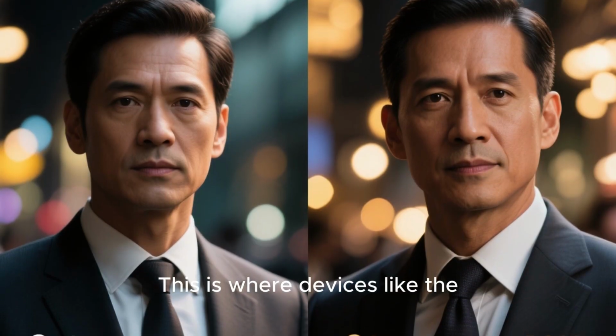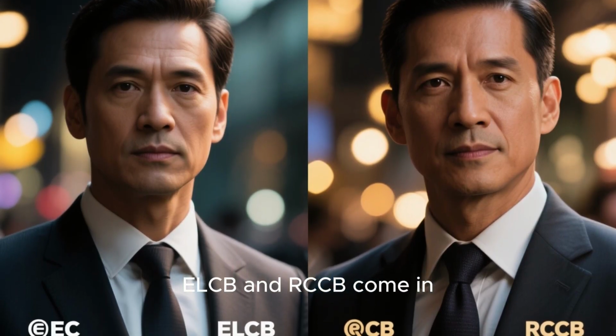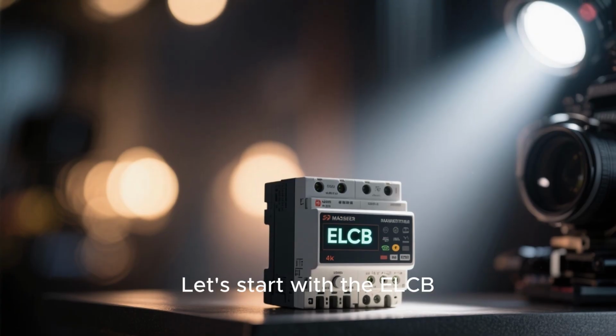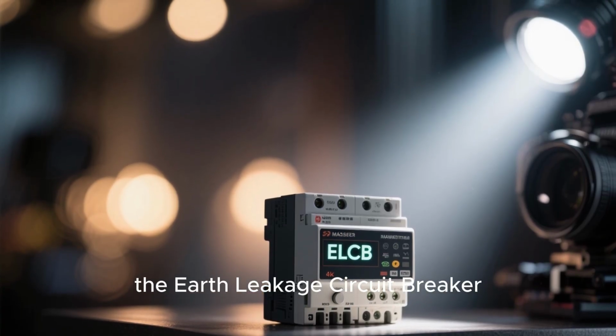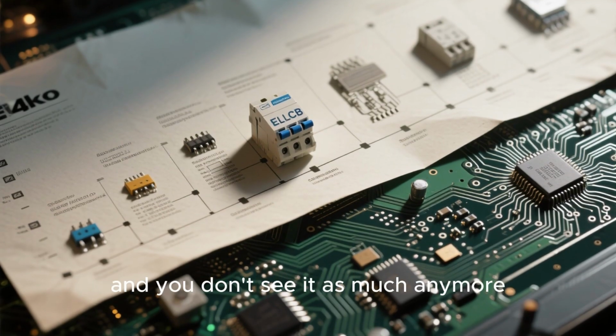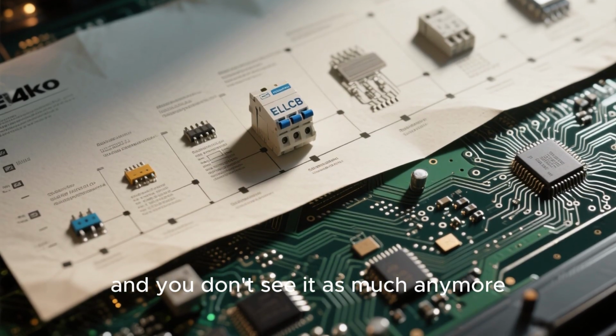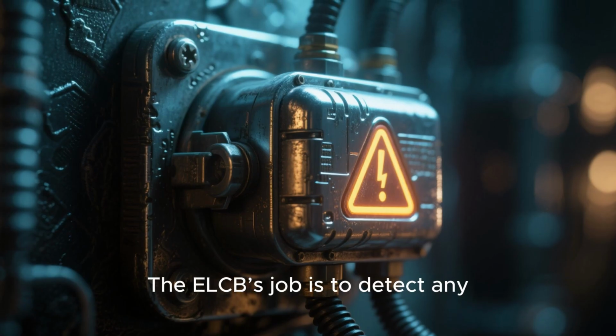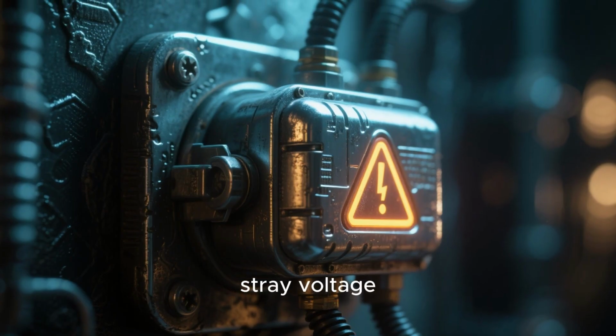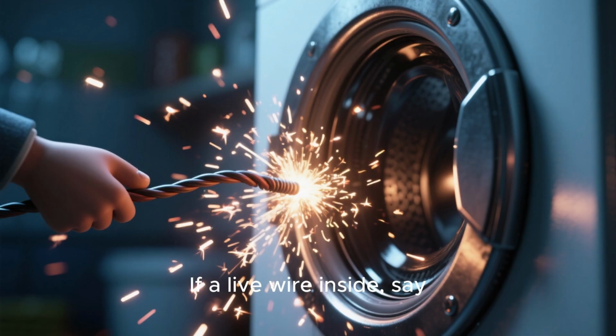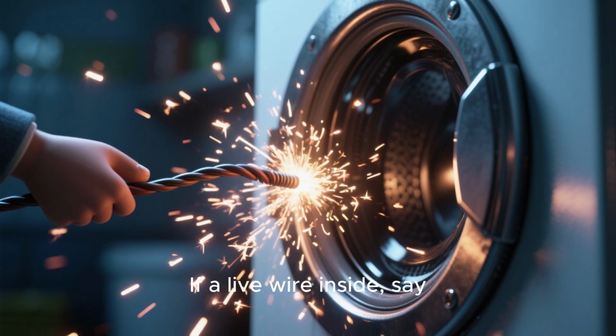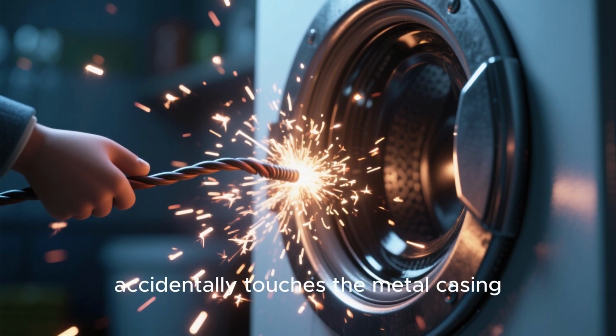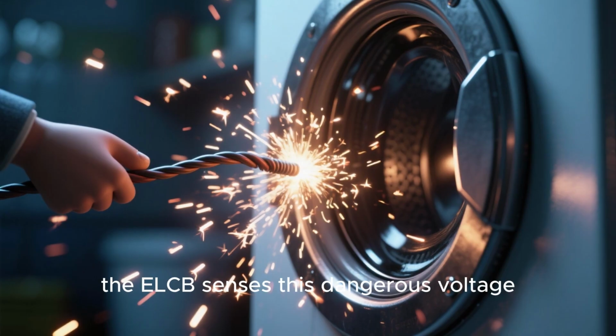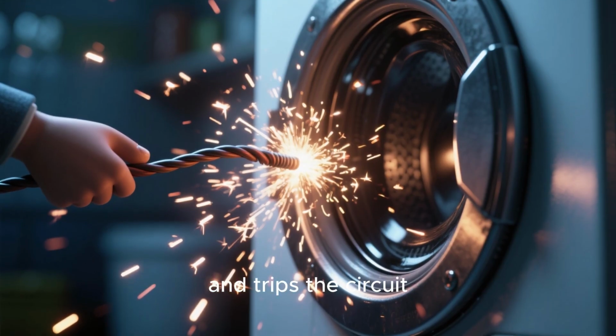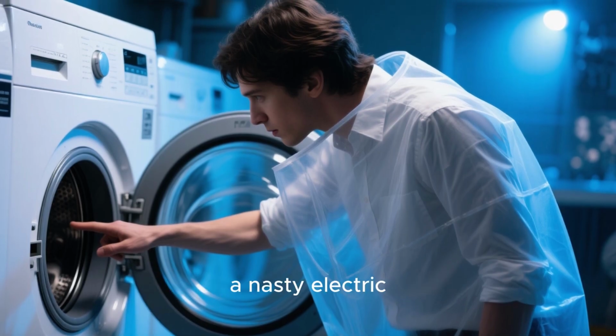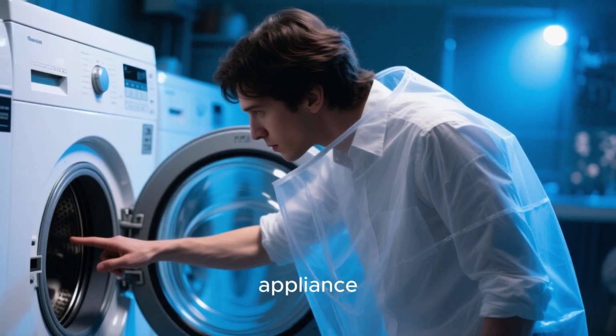This is where devices like the ELCB and RCCB come in. Let's start with the ELCB, the Earth Leakage Circuit Breaker. This is an older technology, and you don't see it as much anymore, but it's important to know. The ELCB's job is to detect any stray voltage on the metal body of an appliance. If a live wire inside, say, your washing machine, accidentally touches the metal casing, the ELCB senses this dangerous voltage and trips the circuit. This prevents you from getting a nasty electric shock if you touch the appliance.